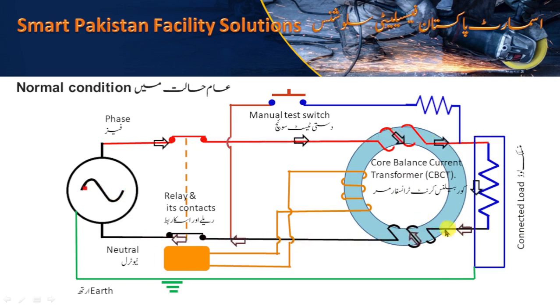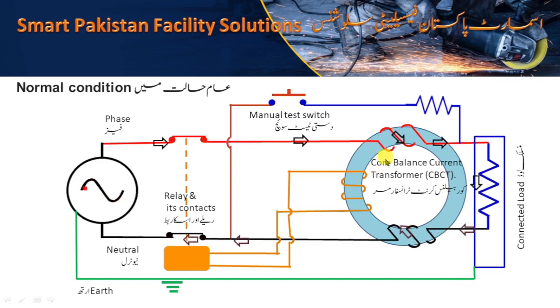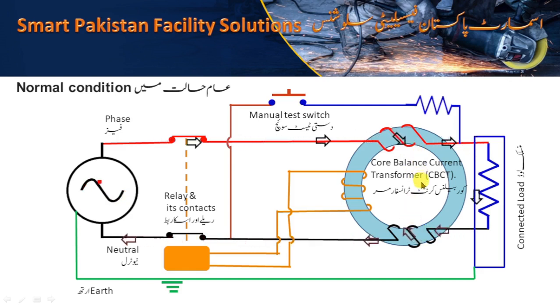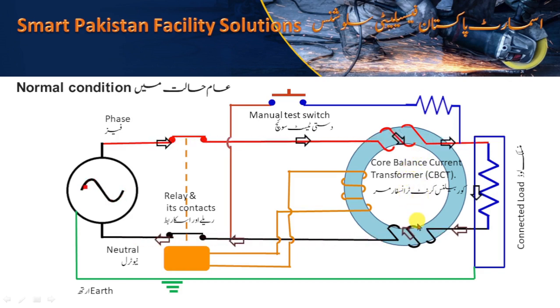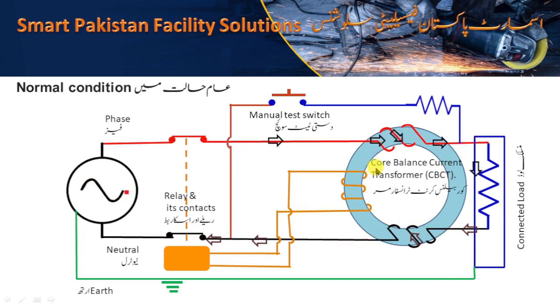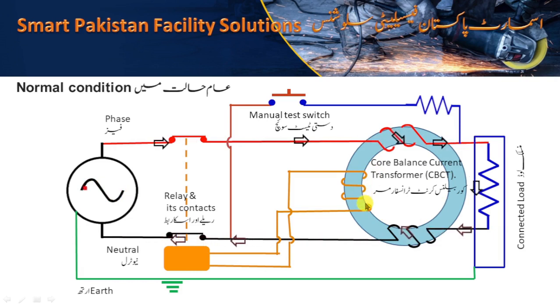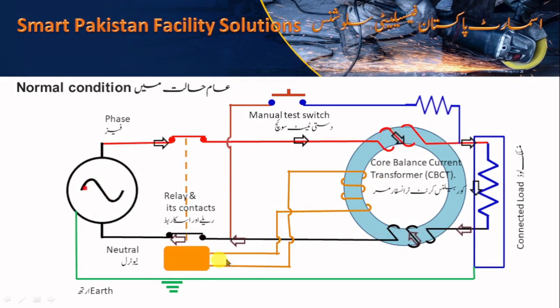This is in this direction and this is in this direction. As per Fleming's law, the flux will be induced in both conductors. But as the magnitude is the same and the direction is opposite, they will cancel the effect of each other. There will be no residual flux in the CBCT. As a result, no current will be induced in the residual current coil, and the system will work normally.